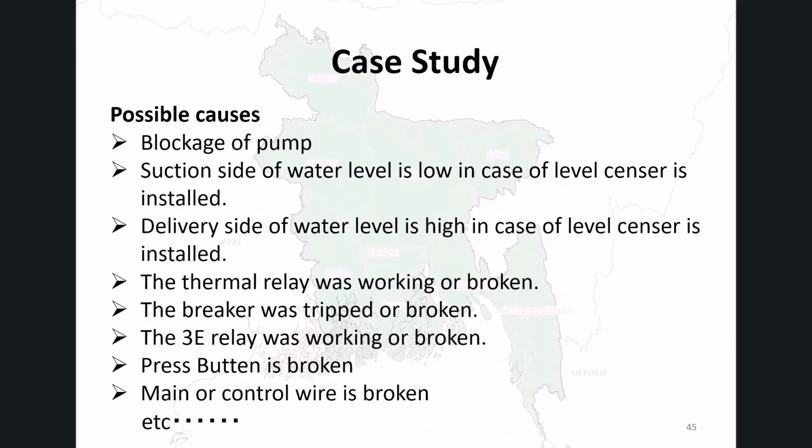It is also possible that the breaker has tripped and cut off the power supply. In addition, the 3E relay may have been activated, the push button may be faulty, or there may be a disconnection in the main circuit or control circuit wiring. As shown above, please list all possible causes that could be considered.